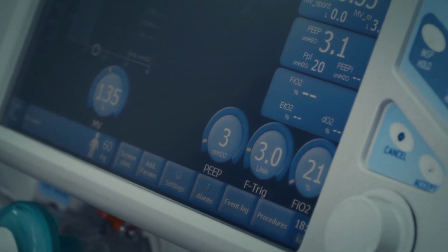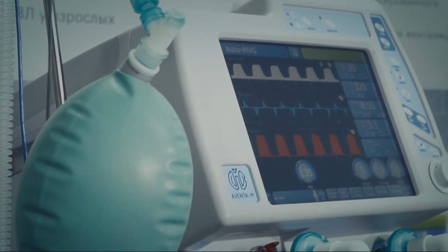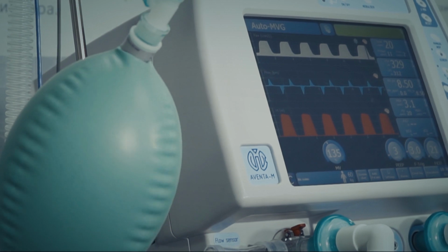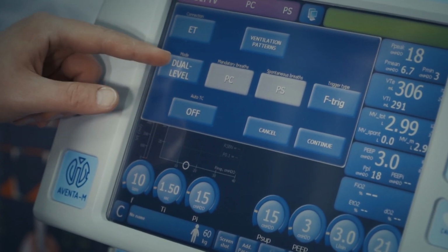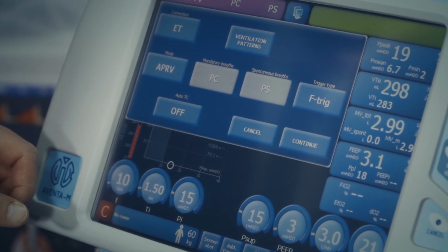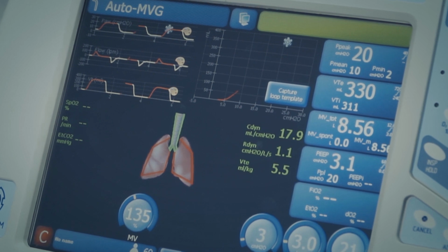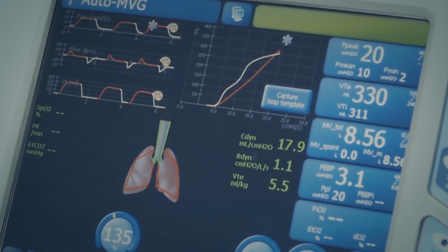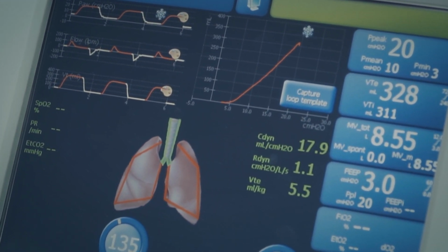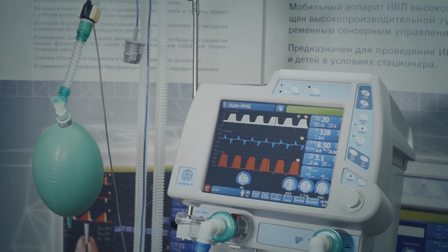Built-in turbine ensures high ventilator performance and allows to reach the peak inspiratory flow rate of up to 200 liters per minute. Big 12-inch high-resolution touchscreen, push-turn knob, and functional buttons are the components of user-friendly interface. To warn the user of any incident, lung ventilator Aventa-M features a 3-level system of visual and audible alarms.